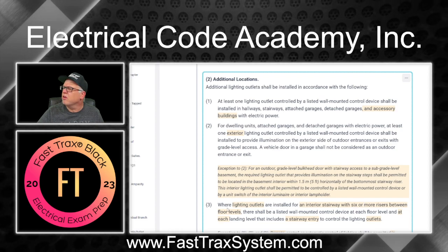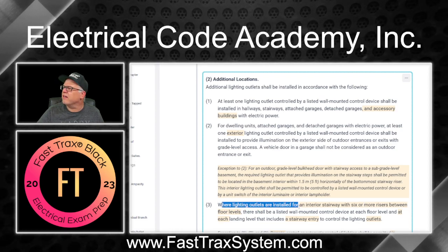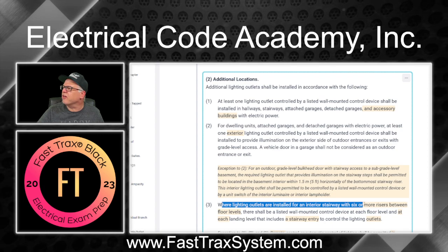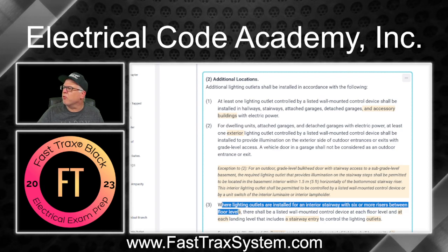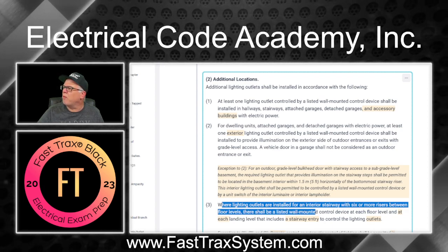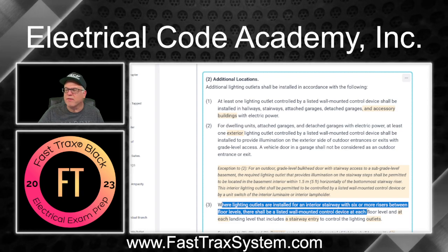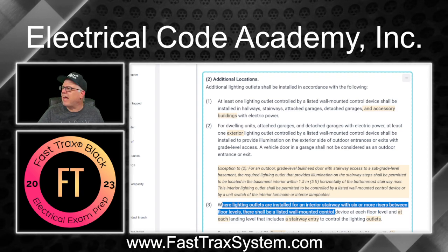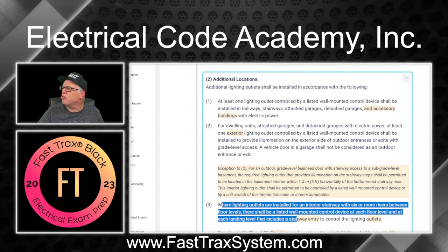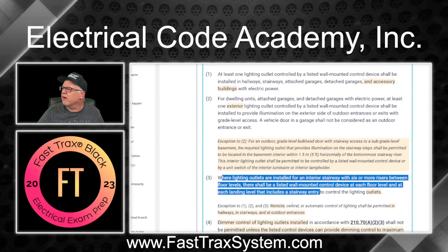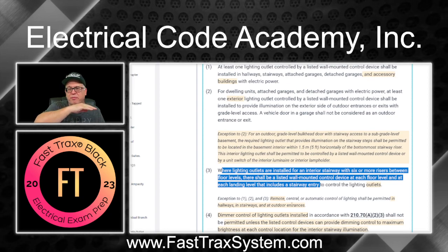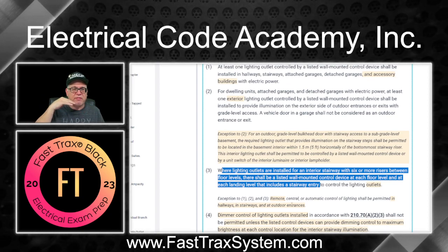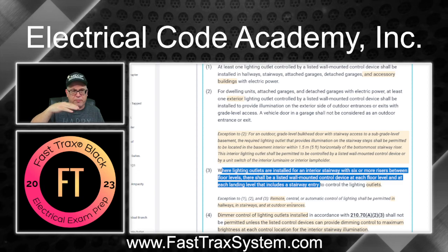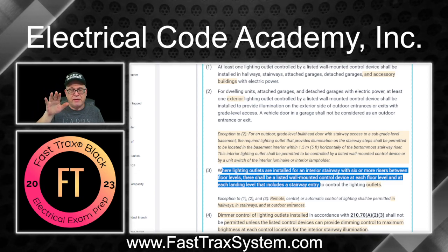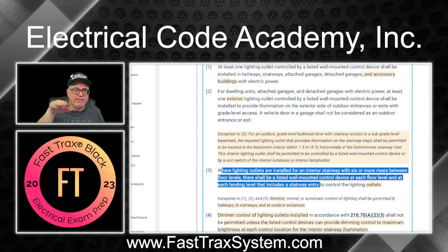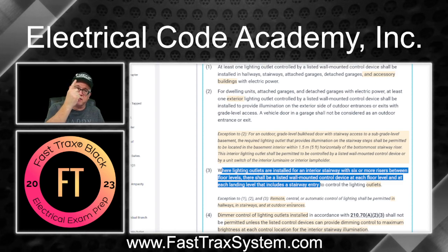And here's what it says: where lighting outlets are installed for an interior stairway with 6 or more risers between floor levels, there shall be a listed wall-mounted control device at each floor level and at each landing level that includes a stairway entry. All right, kind of clarification. So if you have multiple levels and you just have a stairway that goes from first floor to the second floor, and that's it, and even if you have a landing, if you can't leave that landing, then you only need the switching at the top and at the bottom.